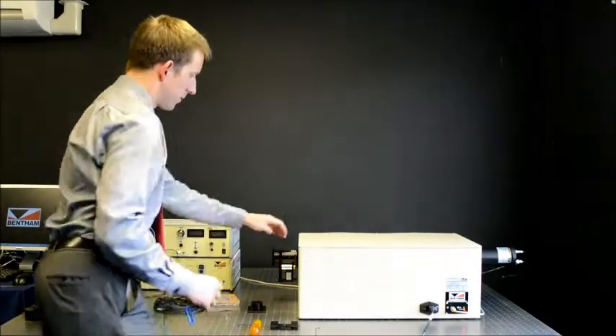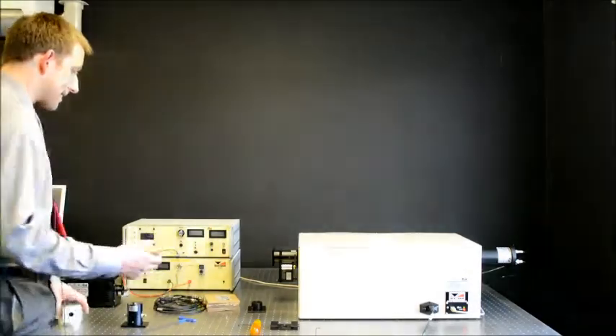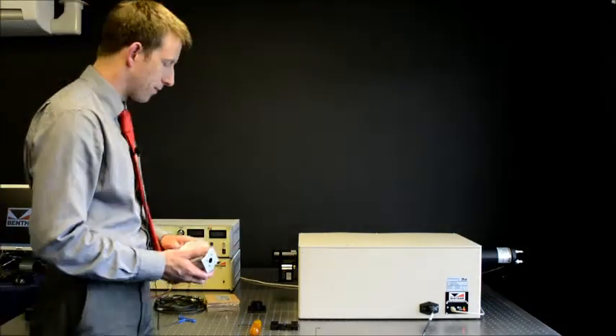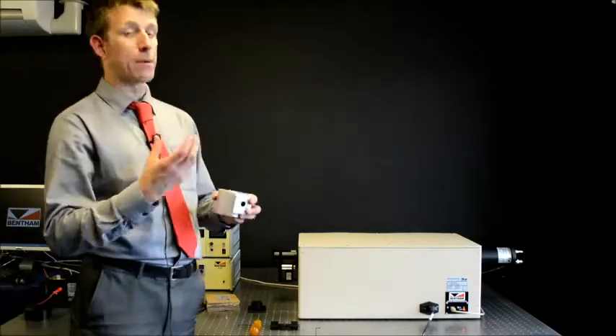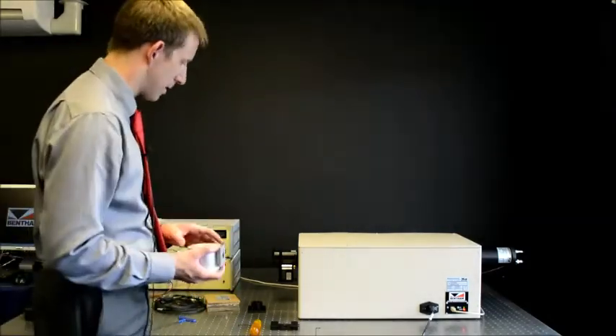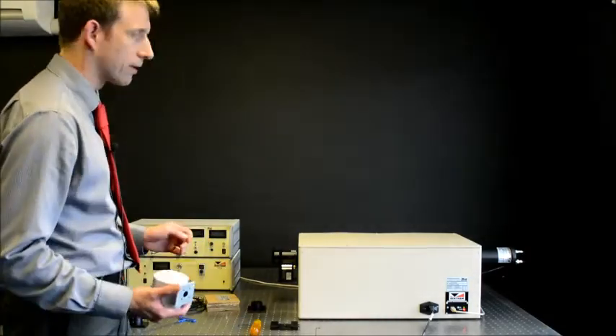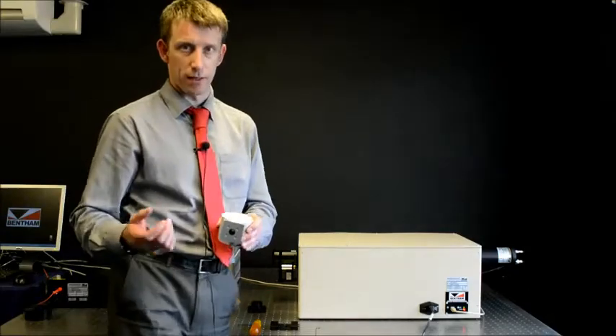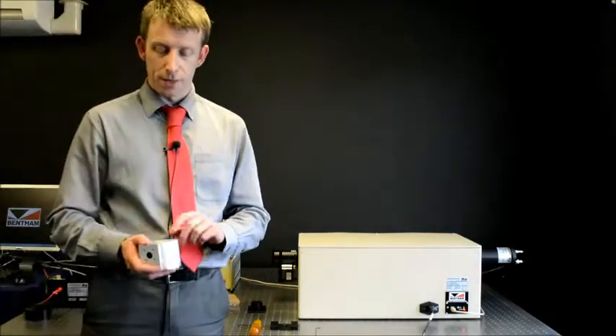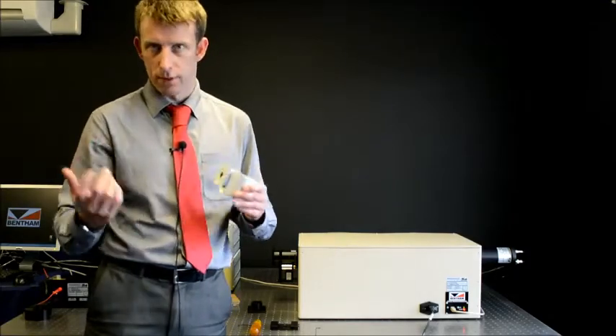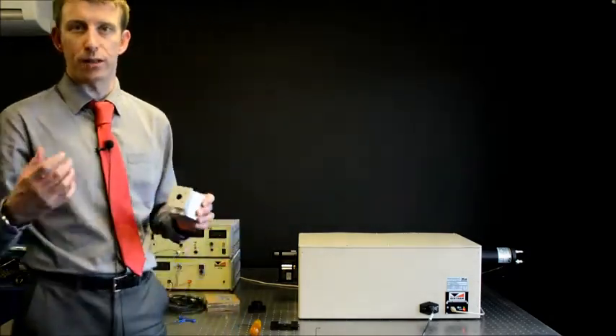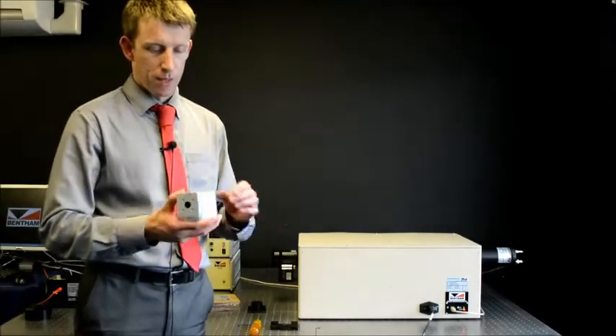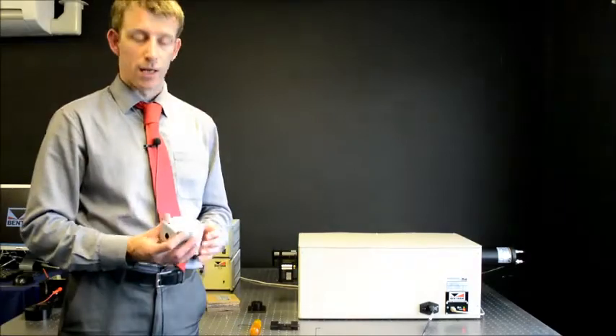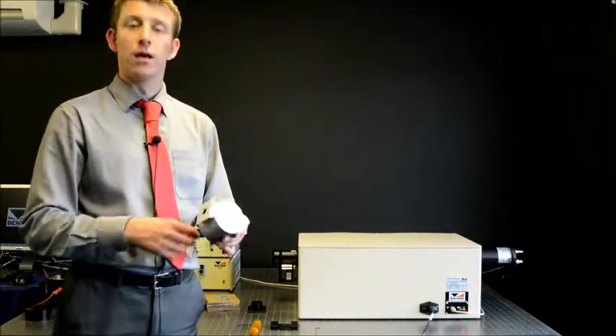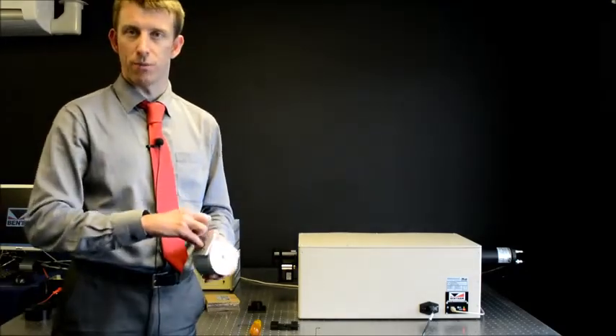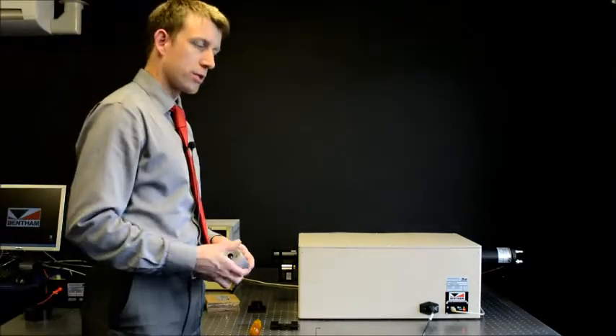Now, the calcium fluoride input optic is in a sense intended for use with the D8 integrating sphere. So the D8 integrating sphere can be used for the measurement of absolute irradiance. In practice, I recommend not to use this item. The reason being that in the infrared, sources emit very little light, detectors are not very efficient. The use of an integrating sphere, or like a diffuser, results in a very great loss in the signal through to the monochromator. Effectively, the light input through the port of the integrating sphere is effectively spread across the area and a very small amount coupled to the monochromator. So we can expect a reduction in signal of perhaps 1/100th.